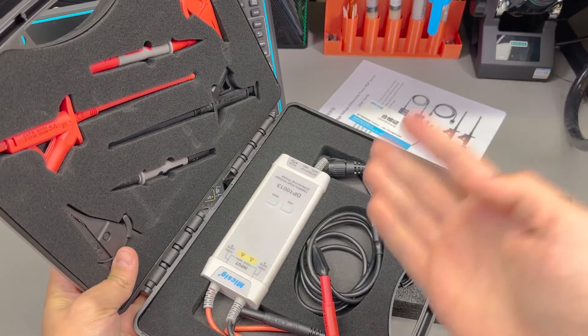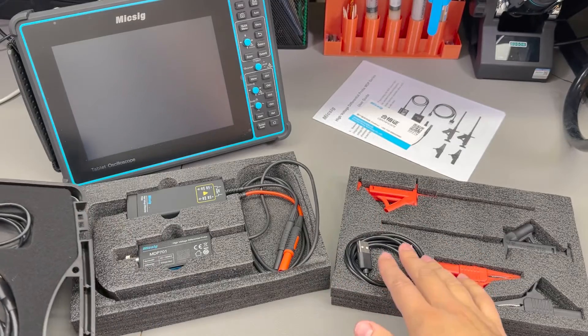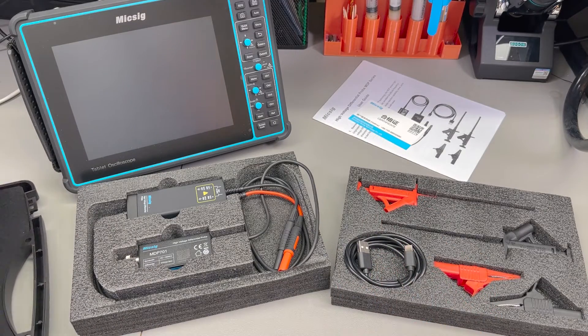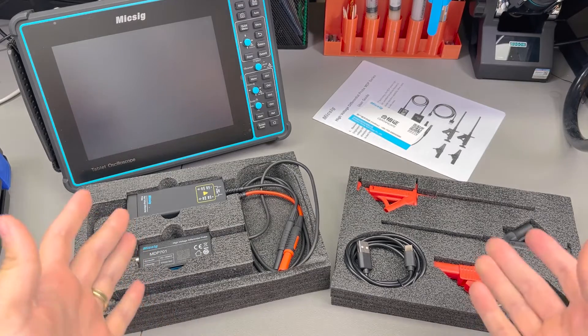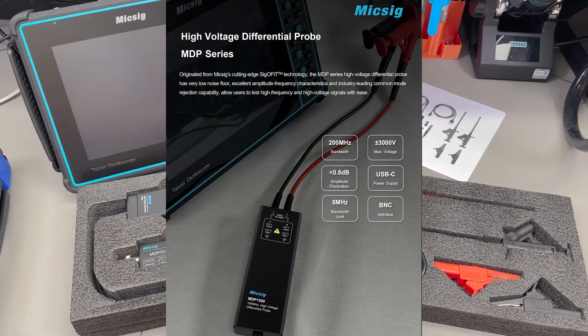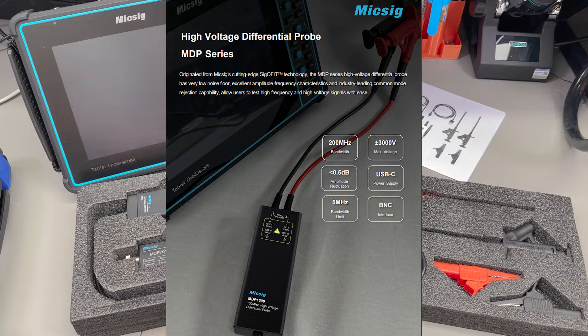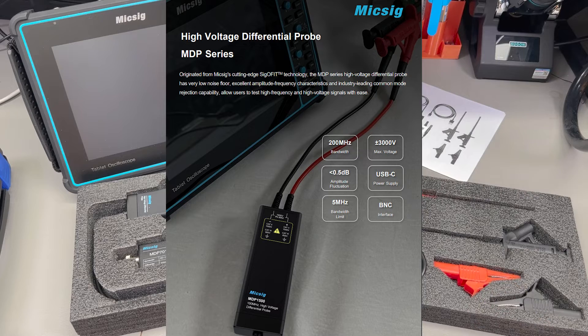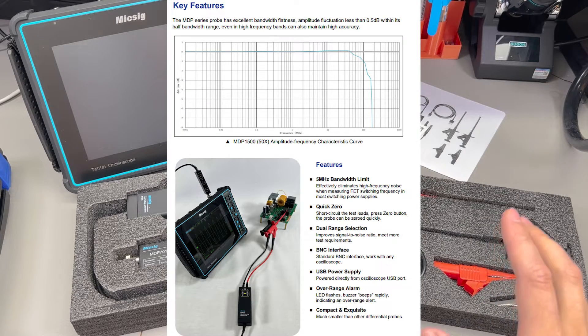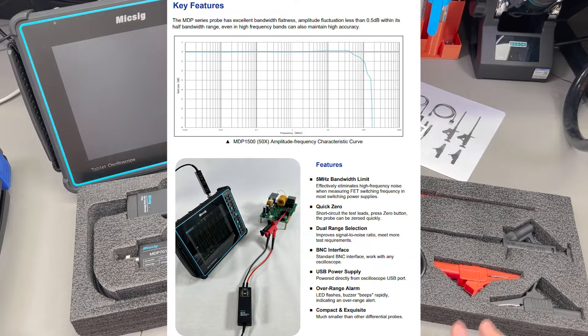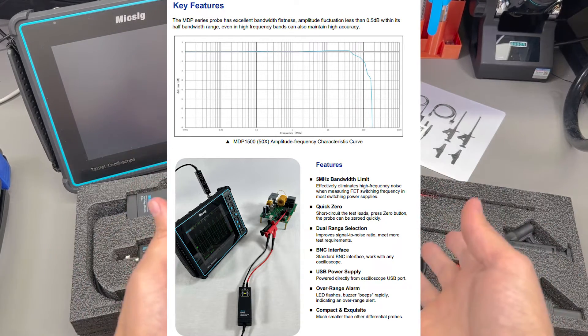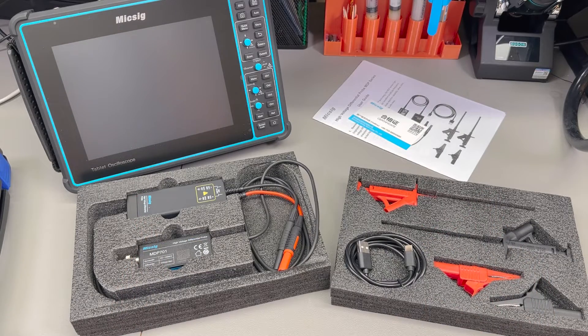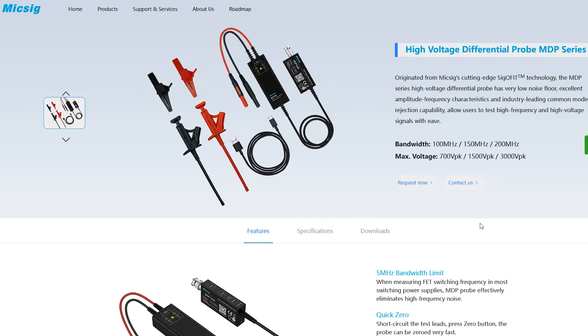So, if Micsig already had a great differential probe, what's the deal with this new MDP series you might ask? Well, first of all there is no reason to stop innovating, this is how you get to the top. It's important to mention that this new MDP series is derived from their cutting edge optical fiber isolated probe which they have trademarked as SigOFIT, so I'm guessing they took at least the front-end analog technology from that lineup minus the fiber optic to put it in this package and make it more affordable for the average consumer that does not need the optical fiber isolation feature.